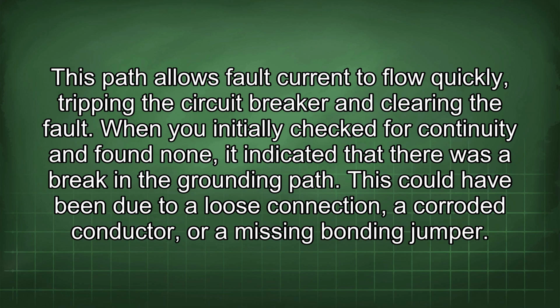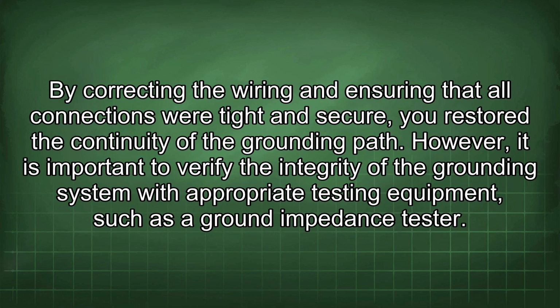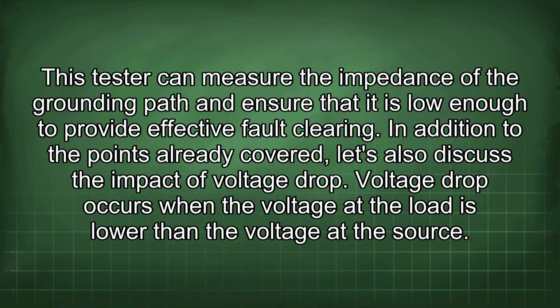When you initially checked for continuity and found none, it indicated that there was a break in the grounding path. This could have been due to a loose connection, a corroded conductor, or a missing bonding jumper. By correcting the wiring and ensuring that all connections were tight and secure, you restored the continuity of the grounding path. However, it is important to verify the integrity of the grounding system with appropriate testing equipment, such as a ground impedance tester. This tester can measure the impedance of the grounding path and ensure that it is low enough to provide effective fault clearing.